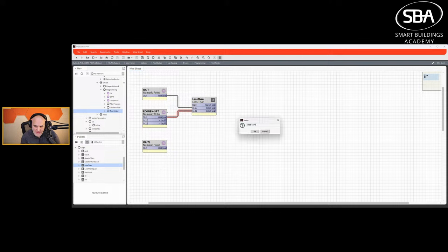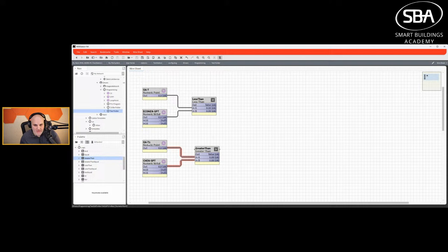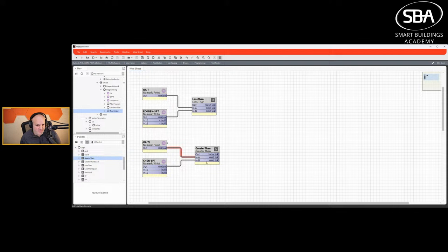This comparative pattern typically enables your chillers and boilers — it may change to a greater-than in the case of a chiller. Let me create another example: if outside air temperature is greater than chiller enable setpoint, then I enable my chiller. You wouldn't create two separate physical variables for outside air in a real program — you'd create one from the physical point on the controller and map it to all your logic blocks.